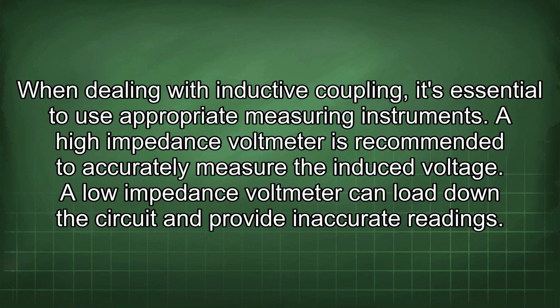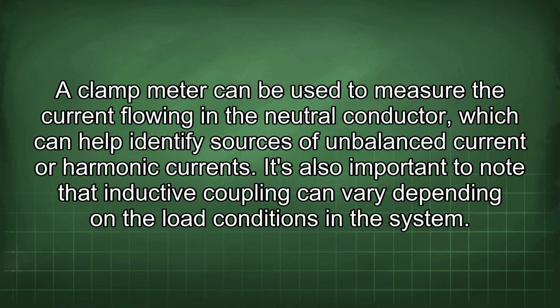When dealing with inductive coupling, it's essential to use appropriate measuring instruments. A high impedance voltmeter is recommended to accurately measure the induced voltage. A low impedance voltmeter can load down the circuit and provide inaccurate readings. A clamp meter can be used to measure the current flowing in a neutral conductor, which can help identify sources of unbalanced current or harmonic currents.